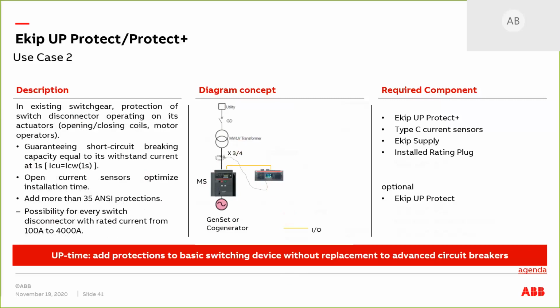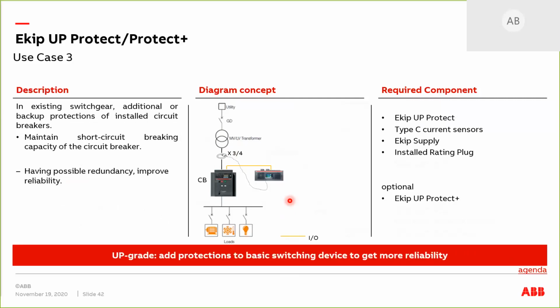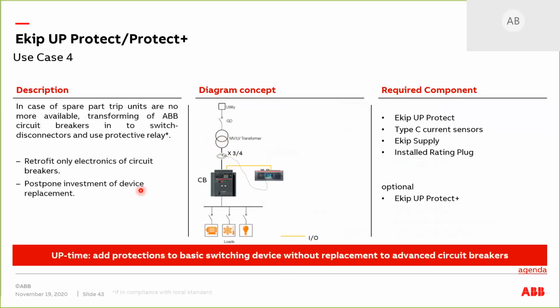With the Rogowski coil, we don't need to make any changes on the bus bar. We just need to wrap the Rogowski coil around the bus bar. Same for the Ekip UP. Then for the I/O, if the Ekip UP senses something that is beyond its parameter, it will send a signal to the breaker. In case there are spare trip units, you can retrofit any electronics of the circuit breaker and postpone investment to device replacement. These are the things that our solution can provide with your existing switchboards.